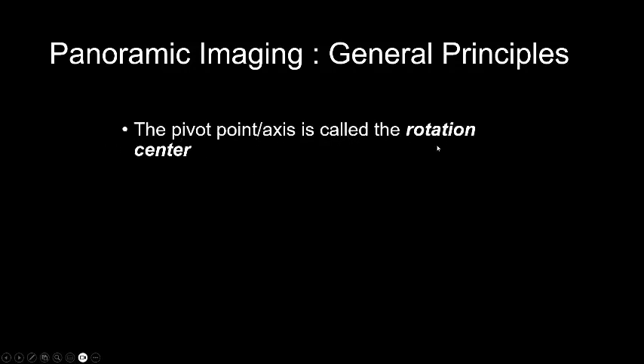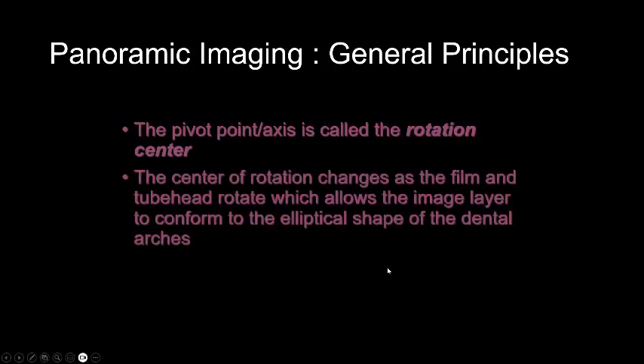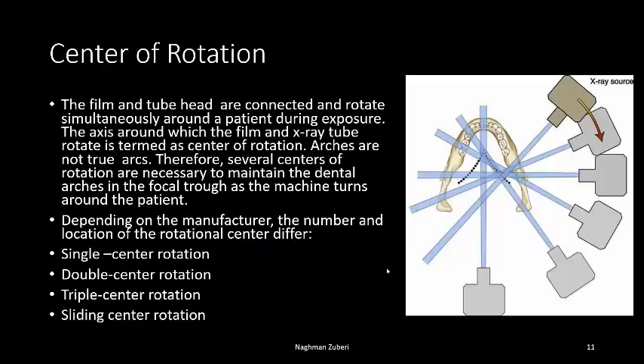The pivot point or axis is called the rotational center. The center of rotation changes as the film and tube head rotate, which allows the image layer to conform to the elliptical shape of the dental arches. Because dental arches are not true arcs, several centers of rotation are necessary to maintain the arches within the focal trough. Depending on the manufacturer, the number and location of rotational centers differ — it can be a single, double, triple, or sliding moving center rotation.